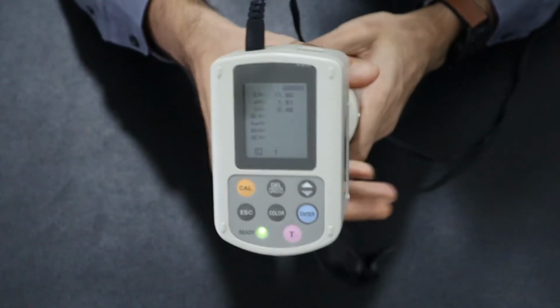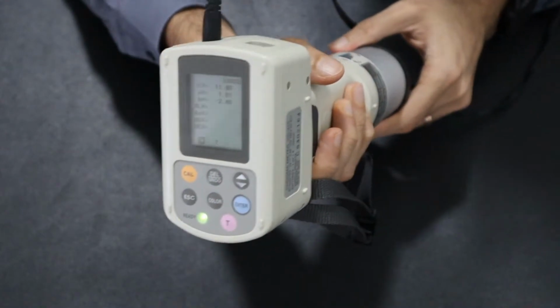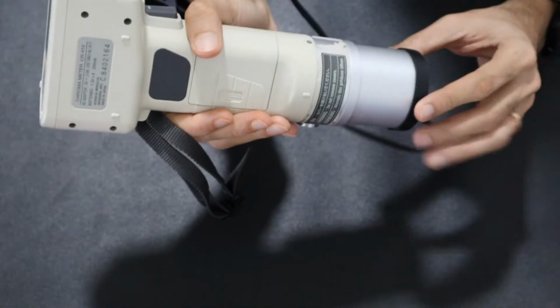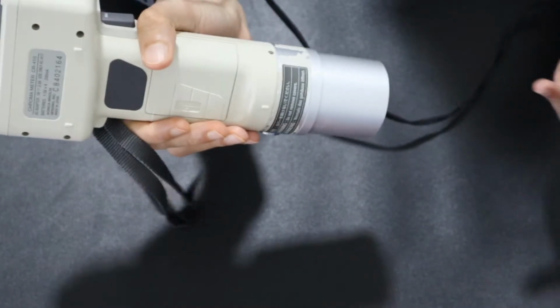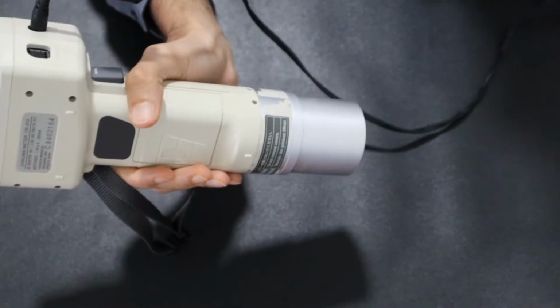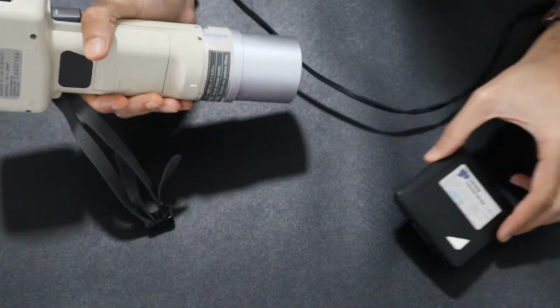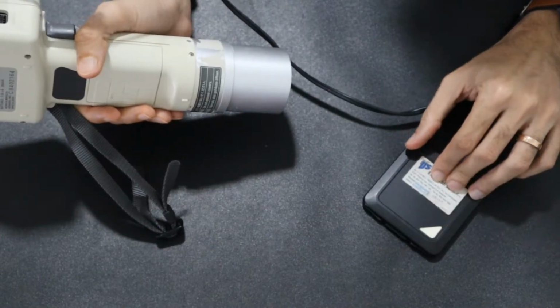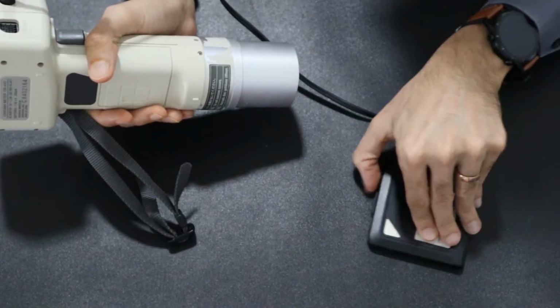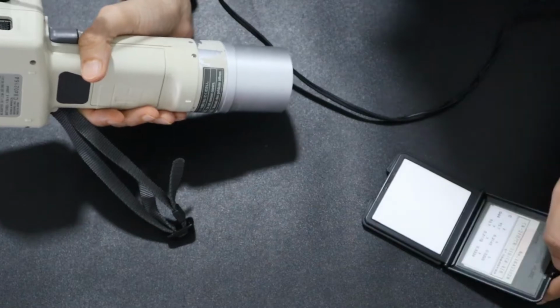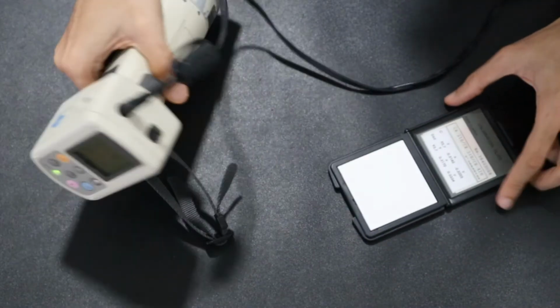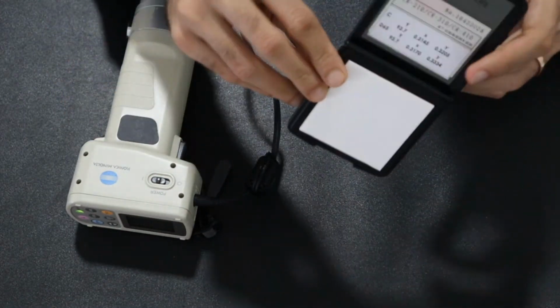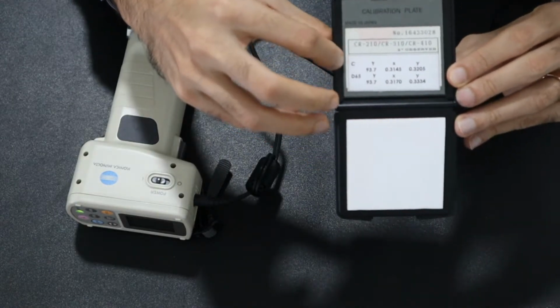So the first step would be to perform the calibration. To do so, remove the protective cap, place it aside, and bring along the white calibration plate which is supplied. Okay. So you open up the white calibration plate like this, and you will notice that on the white calibration plate there will be some data over here.